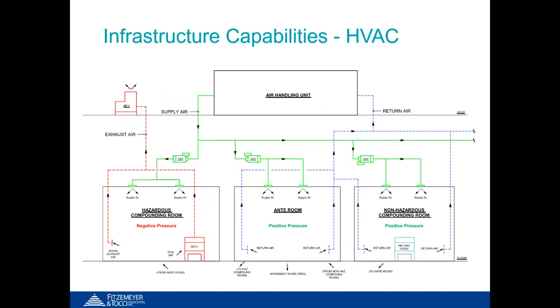Using the anteroom as an example, return air travels back to the unit through low return air grills. This is true for the anteroom as well as non-hazardous compounding rooms. In the hazardous compounding room, both the hood as well as the room exhaust air are removed from the space through a dedicated exhaust system. In this example, the air handler meets all of the air change requirements, the HEPA filtration requirements, as well as providing temperature and humidity control.